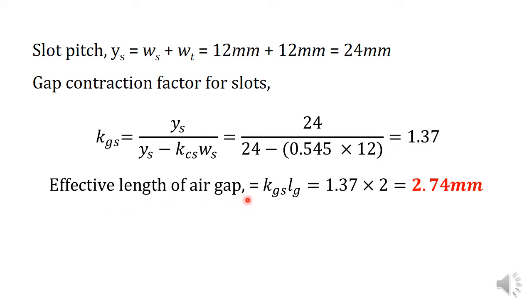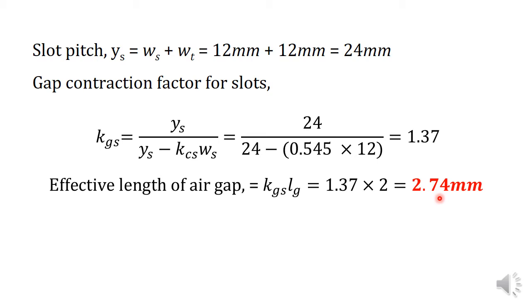The effective length of air gap is equal to the product of the gap contraction factor and the length of air gap. That is KGS into LG, which is 1.37 into 2, equal to 2.74 mm. So even though the actual length of air gap is 2 mm, due to the presence of slots, the effective length of air gap has become 2.74 mm.